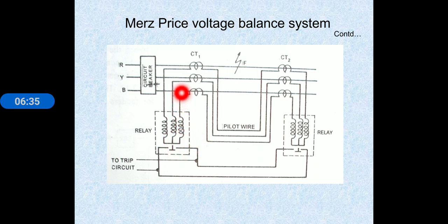But if any abnormal condition occurs, meaning any fault occurs in this line, then the entering and leaving currents of these lines become unequal. At the same time, the secondary voltages of the current transformers also become unequal. Let's take an example. In normal conditions, assume the secondary voltage of this current transformer is 5 volts. Here also it is the same voltage, so in normal conditions the voltages are equal. When an abnormal condition occurs, this side voltage may remain 5 volts, and the current transformer 2 side voltage may become 10 volts. There is an increase in voltage, so the voltages become unequal.